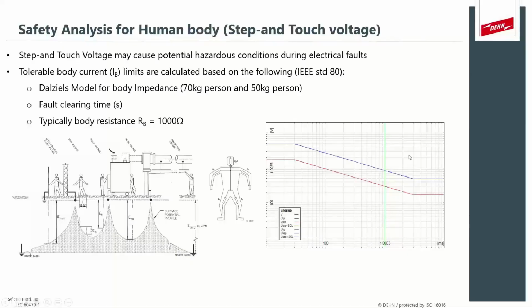And at the end of the calculation, this graph is given, which illustrates the step voltage limit for a human being, in this case a 50 kilogram person, with the blue line, and the touch potential limit on the red line. The voltage is on the y-axis and the tripping time is on the x-axis. So the tripping time is the fault clearing time, when the circuit breakers will clear the fault. You can see that the longer the tripping time becomes, the lower the limit becomes, as the shock duration will increase. And as the tripping time gets shorter and shorter, the voltage limit actually increases, and the human body can take a little bit more.